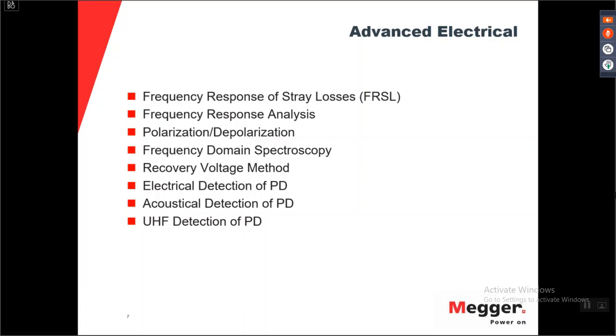So for these 3 tests, PDC, FDS, and RVM, there is not a big difference. The only difference, I should say, is basically how you apply the voltage, but the result of the test is actually the same. So you don't do all of them, you only do one of them. And as I said, I cannot cover all the advanced electrical tests because for the partial discharges, I don't have sufficient knowledge, and we have the factory in Aachen that knows very much about all the partial discharge tests. So we can also have a separate seminar for that, or it might already have taken place.